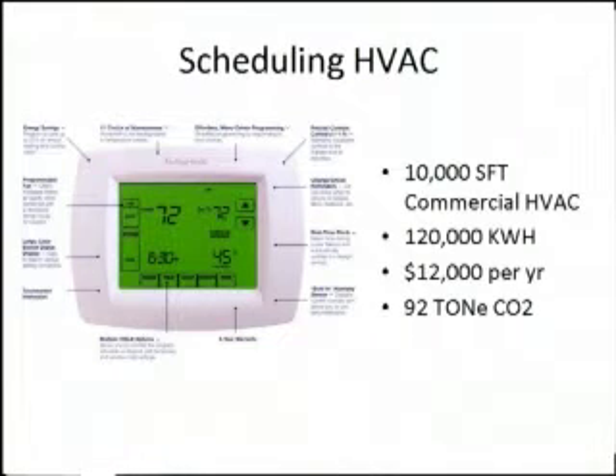Scheduling is another really powerful tool. I'm sure that you're taking advantage of it by now, but these are available now at Home Depot, everywhere else for $30 or $40. This is about a $200 thermostat here that's more of a commercial model, and it gives you a little bit more freedom, but it'll hold multiple time schedules, so we can schedule this DX equipment. We can schedule not only the cooling, but also schedule the ventilation independent of each other, and take advantage of even additional savings. So for a 10,000 square foot facility, I estimate the HVAC costs to be about $12,000 a year. So if we can cut that by half or a fourth or whatever, we're talking about big dollars on an annual basis.